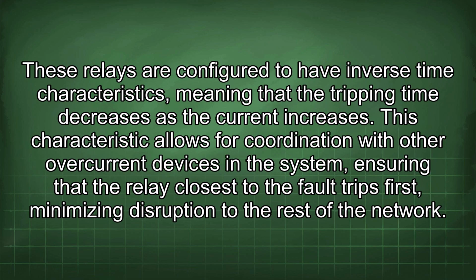These relays are configured to have inverse time characteristics, meaning that the tripping time decreases as the current increases. This characteristic allows for coordination with other overcurrent devices in the system, ensuring that the relay closest to the fault trips first, minimizing disruption to the rest of the network.